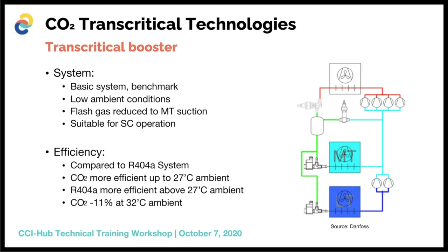So studies have been done to show what the efficiency gains can be from the transcritical booster, which is taken as the benchmark, and then adding additional technologies to get more energy efficiency when you're running at higher ambient conditions. So basically for the transcritical booster system, a lot of studies have found that up to an ambient condition of about 27 degrees Celsius, the CO2 system is more efficient than a standard R404A system, also making use of variable speed drives and electronic expansion valves. So basically, that's why I say mostly subcritical operation for a transcritical booster system.